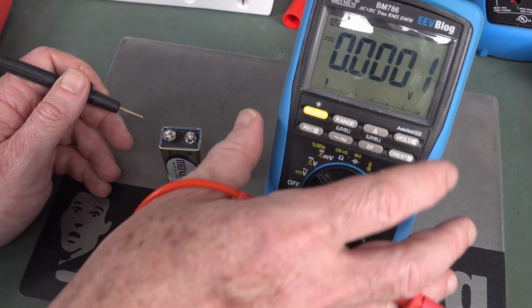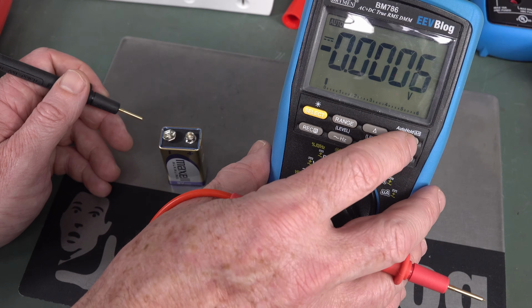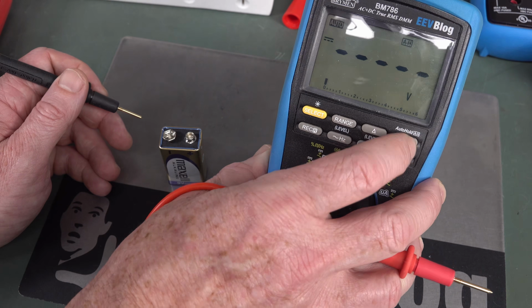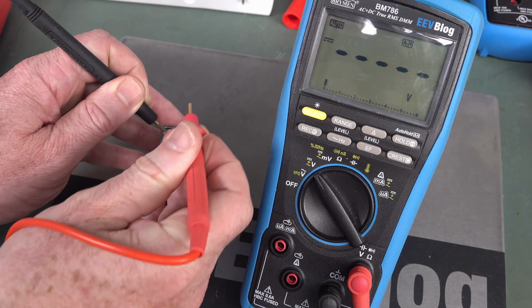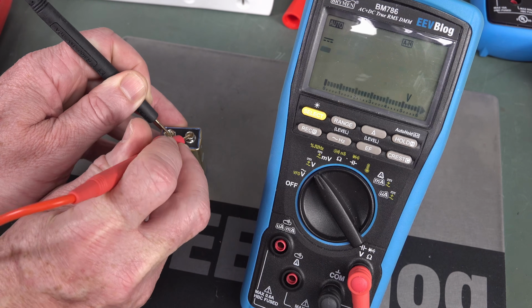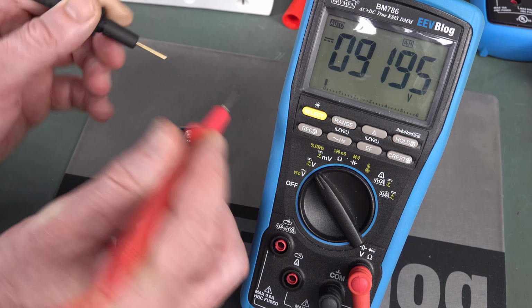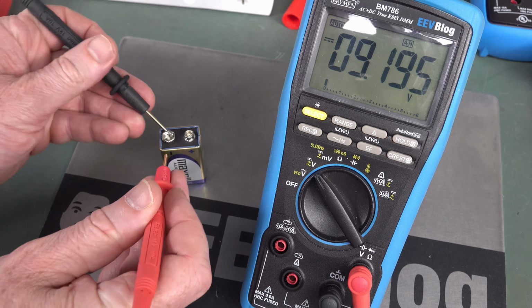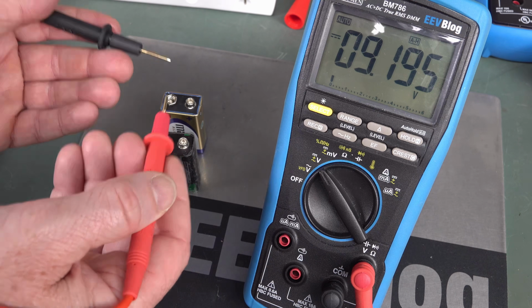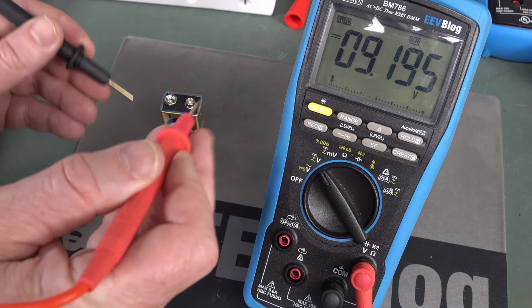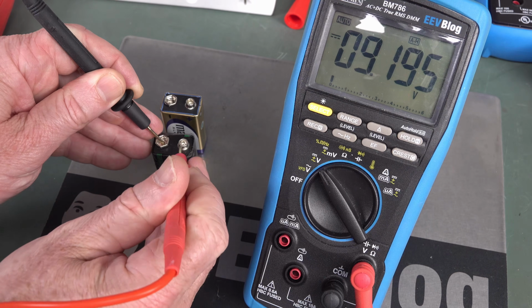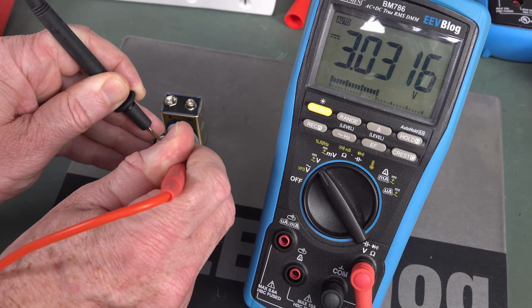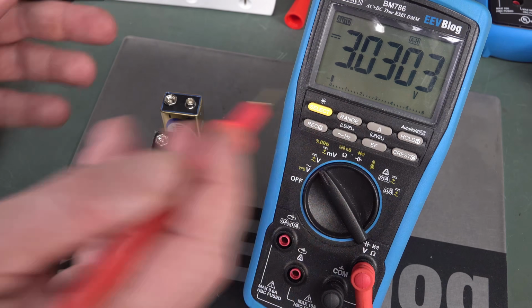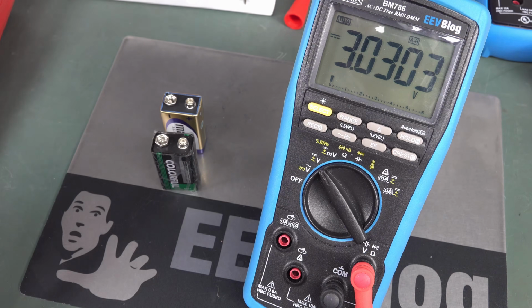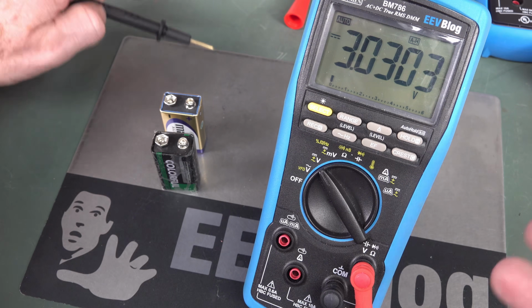Don't do it. Now, some meters have an auto hold or touch hold function, as it's called. If you enable that, it can be really handy for tricky probing. So if I just probe that briefly, it locks in, and then I take my probes away and the reading is still there, locked in for me. It basically waits for a stable reading, and once it's found it, it locks it in for you. Very handy, and then it's ready to go again. If we get another battery here and probe that, it's locked in, it beeps, and then it flashes that reading, hands-free. So not an essential feature, but it's pretty darn handy.